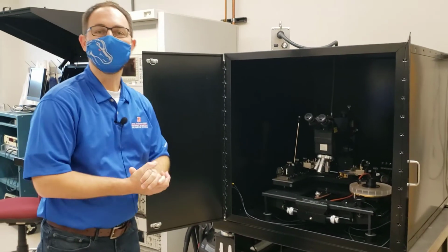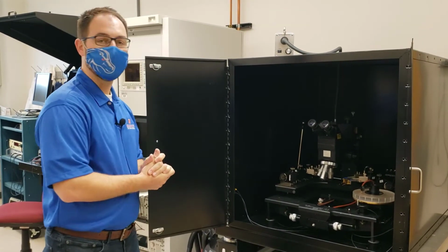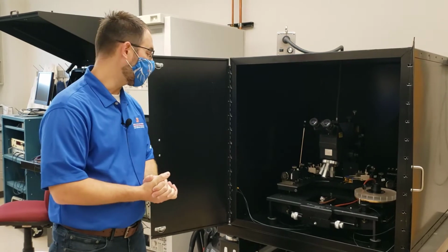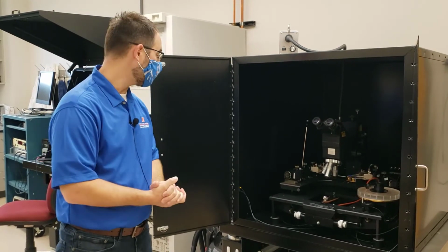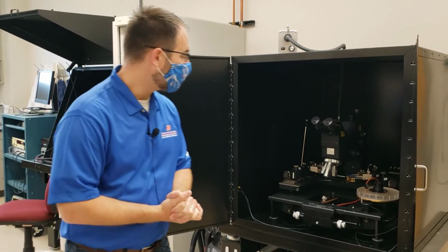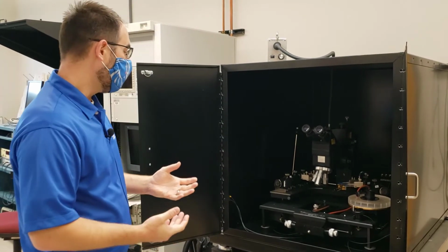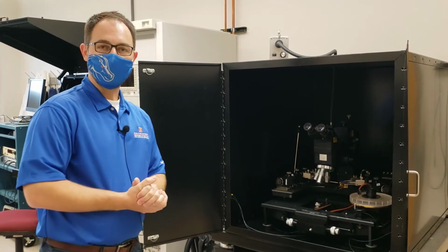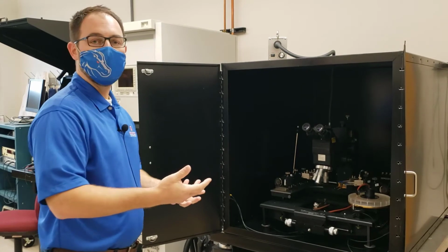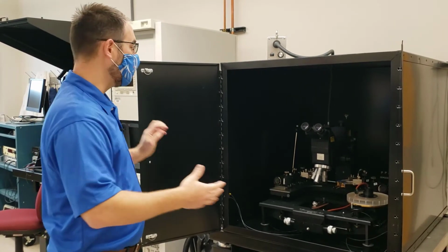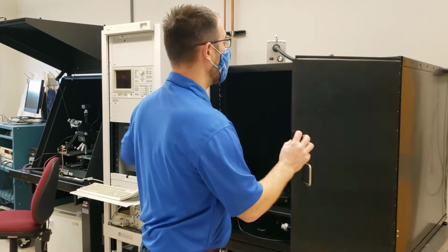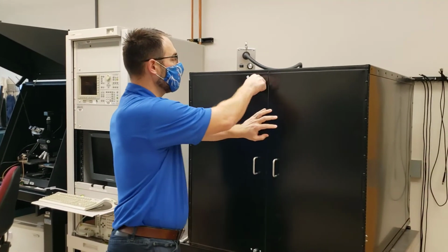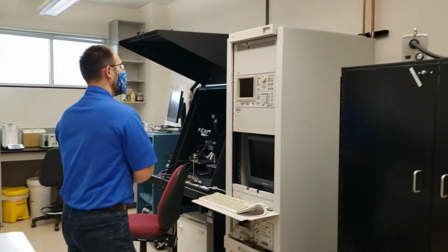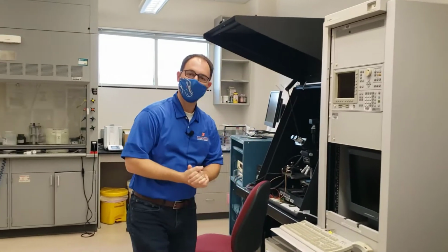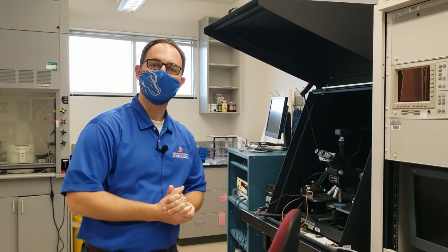So in our lab, one of the things we have is a pretty large microprobe station, contained inside of a black box Faraday cage for grounding purposes, to minimize electromagnetic noise and light interference. We have several wafer microprobes in here and a high-powered microscope to look at your sample and place the probes, and then connect over to our rack of Agilent characterization equipment right over here, which includes your normal semiconductor parameter analyzer as well as oscilloscopes and function generators.